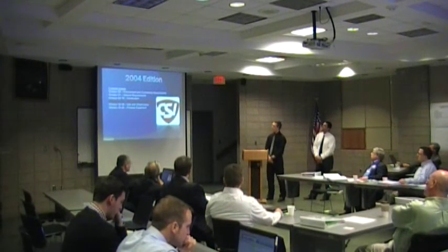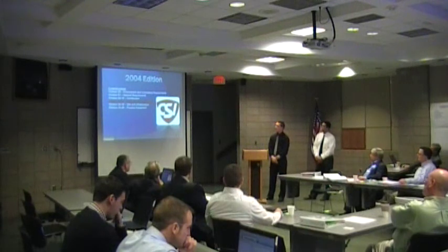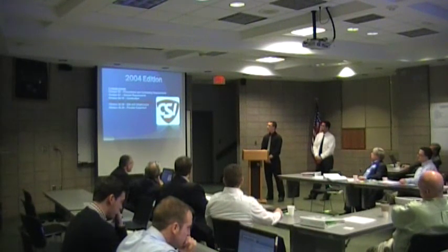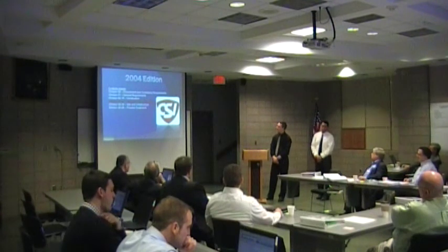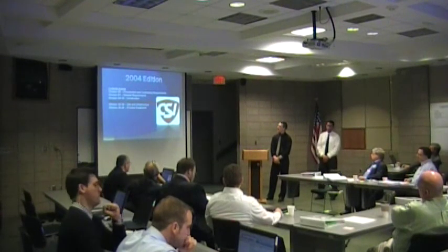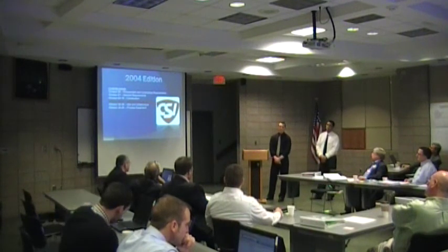00 is procurement and contractor requirements. 01 is your general. 2 through 19 is your construction. 20 through 29 is our facility services subgroups, which is where we're located. Divisions 30 through 39 is your site and infrastructure. 40 through 49 is your process equipment.